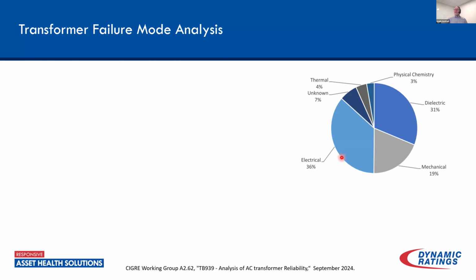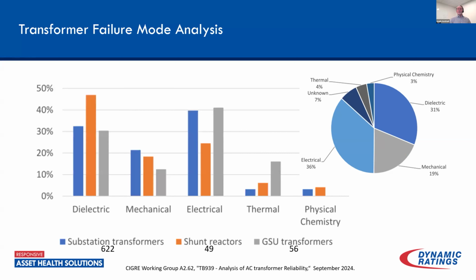What we're seeing is that regardless of the application, the percentages change, but the failure modes don't. So here we're seeing electrical is a big piece of this. Electrical failures, dielectric failures, mechanical failures, things like that. When I talk mechanical, pretty much you're talking more on the through fault side of things. Obviously those types of failures are probably more prominent on the distribution side, maybe a little bit on the transmission side, but less when it comes to the transmission-based or the generator step-up based assets.